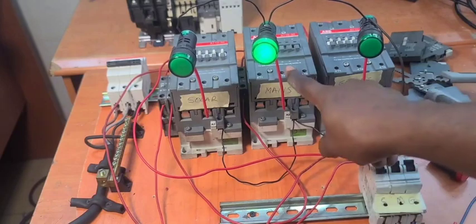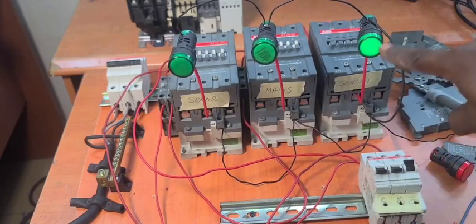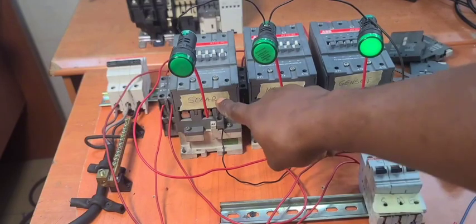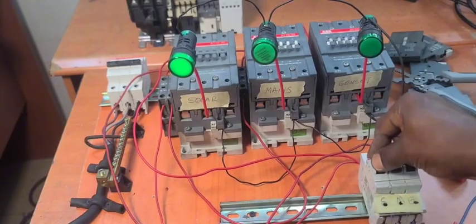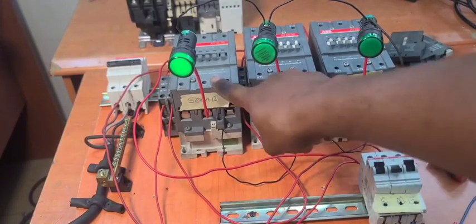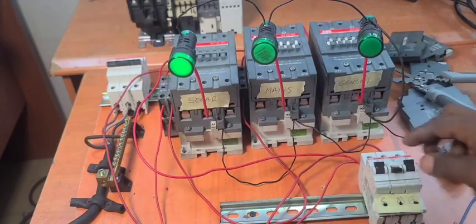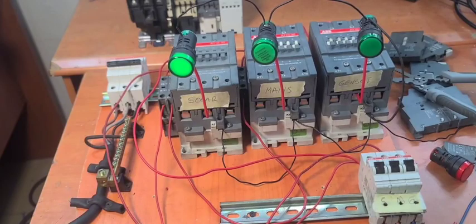It can only come on when this one is not engaged and this one is not engaged. So let us switch off mains. And you see genset is on. Now when genset is on and solar comes up again the next morning like this, it will shut off this one and this one will be on. All right. Okay, let us say mains is on like this.